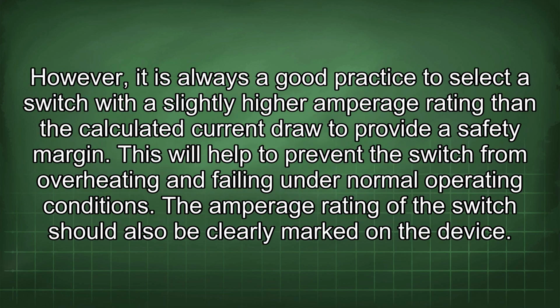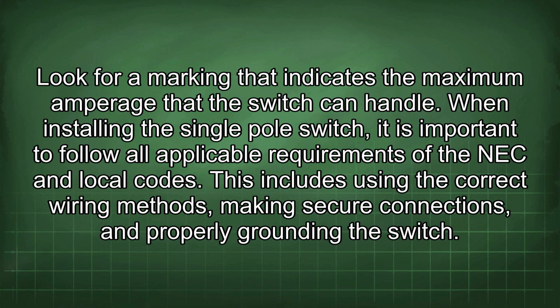However, it is always a good practice to select a switch with a slightly higher amperage rating than the calculated current draw to provide a safety margin. This will help to prevent the switch from overheating and failing under normal operating conditions. The amperage rating of the switch should also be clearly marked on the device. Look for a marking that indicates the maximum amperage that the switch can handle.